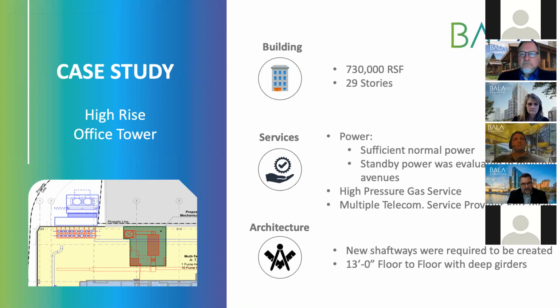As our initial assessment, we did notice that we had sufficient power, thankfully. The office building itself turned out to have been designed with a little more power than what you would normally find in an office building, and we also had the advantage of a couple floors being data center. So in the end, we found that we had enough normal power coming into the building.